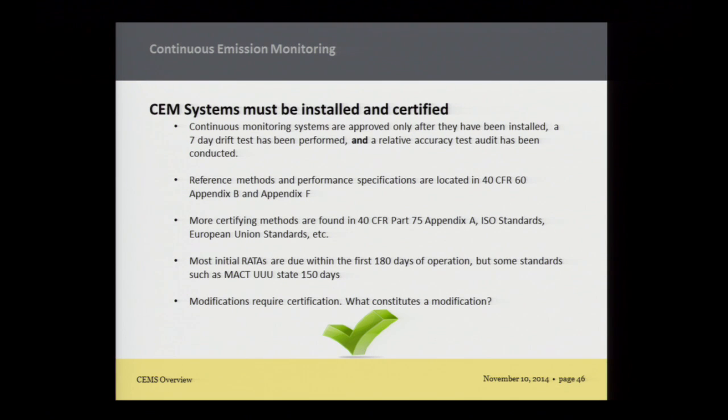What if it was 3 runs less than 1 hour? If you don't follow the method, you don't have to turn it in. It's an engineering study, just doing that for your own personal knowledge. Yep. So the method could say run an hour, and if I run 45 minutes and do 3 runs and I didn't follow the method, or I calibrated at the beginning but I didn't calibrate at the end, then I didn't do an official run because I didn't follow the method. You could run, say, a 5-hour run just to see what it is in that time. You didn't follow the method because it's laid out. So that's something you can do.